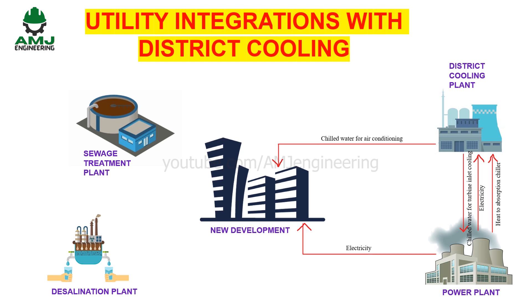Let us go to the heat rejection path. District cooling plants typically use cooling towers to cool the chillers' condensers. Cooling towers require makeup water because some water is lost through evaporation, drift, and blowdown processes.